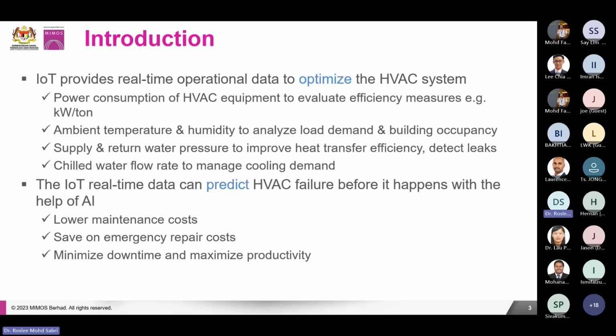Similarly, if we can measure the real-time temperature and humidity of the environment, we can analyze the required load or demand for that particular time, which allows us to put in a strategy to meet this demand. So we don't have to run the chiller at full blast all the time; depending on demand, we can reduce or increase it as required, ensuring the system operates at an efficient point.